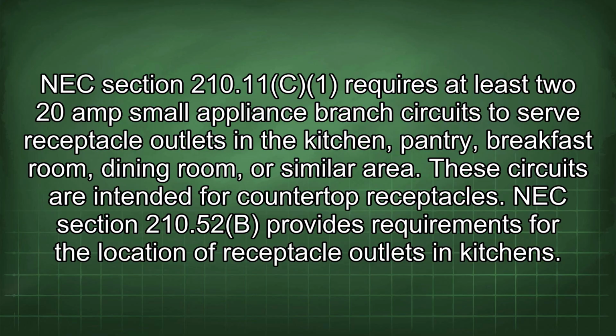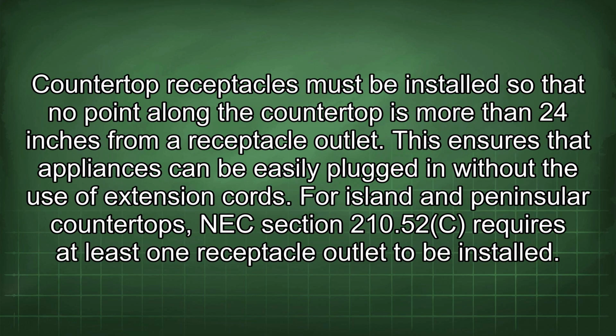NEC section 210.52(B) provides requirements for the location of receptacle outlets in kitchens. Countertop receptacles must be installed so that no point along the countertop is more than 24 inches from a receptacle outlet. This ensures that appliances can be easily plugged in without the use of extension cords.